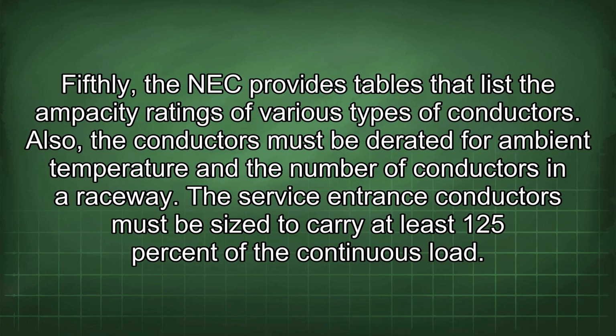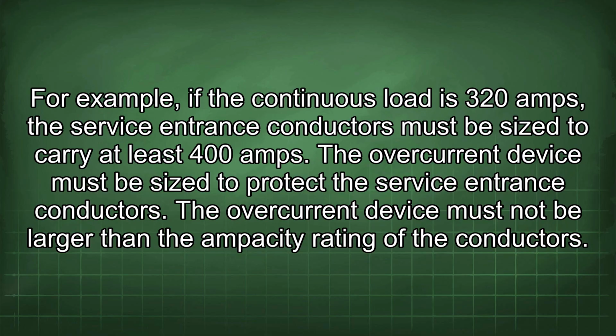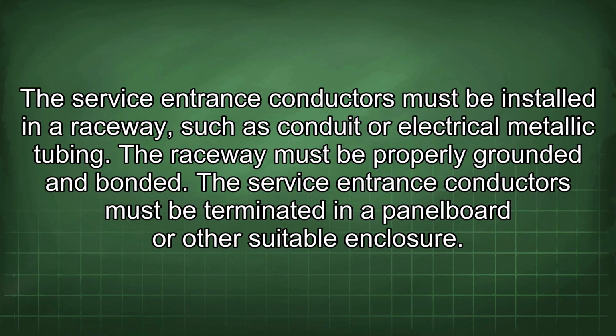Fifthly, the NEC provides tables that list the ampacity ratings of various types of conductors. Also, the conductors must be derated for ambient temperature and the number of conductors in a raceway. The service entrance conductors must be sized to carry at least 125% of the continuous load. For example, if the continuous load is 320 amps, the service entrance conductors must be sized to carry at least 400 amps. The overcurrent device must be sized to protect the service entrance conductors. The overcurrent device must not be larger than the ampacity rating of the conductors. The service entrance conductors must be installed in a raceway such as conduit or electrical metallic tubing.